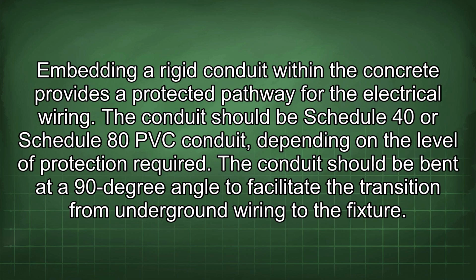Embedding a rigid conduit within the concrete provides a protected pathway for the electrical wiring. The conduit should be Schedule 40 or Schedule 80 PVC conduit, depending on the level of protection required. The conduit should be bent at a 90-degree angle to facilitate the transition from underground wiring to the fixture.